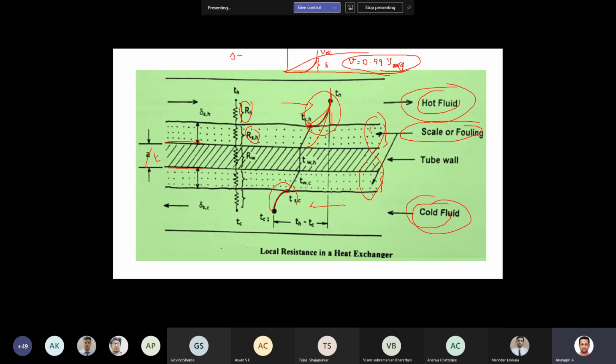They are also called sedimentation fouling, because in the earlier case, precipitation fouling, the substances are soluble in the process fluid and, because of the temperature range, they settle on the surface. But in particulate fouling, they are not soluble in the fluid; they are suspended particles in the process fluid. Over the period they stick to the surface and settle. Sedimentation fouling is possible.